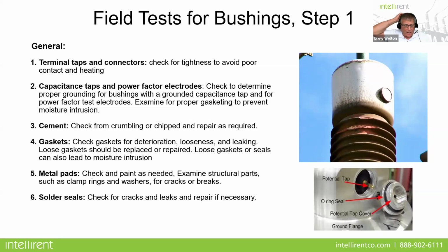And it's funny, I was talking to a colleague just a couple of weeks ago, and he went on site on a recently commissioned transformer to determine why the differential relay tripped. And when he got on site, two things. The first thing he noticed was that all the bushing clamps on the top of the bushing were all loose. They were all just hand tightened. So, they weren't properly torqued down. The second thing he noticed was that they had a rolled CT secondary, which has nothing to do with the bushing. It's just a bad practice in terms of hooking up the connections. And the other thing is that the de-energized tap changer switch was halfway between one tap or the other, which could have been really catastrophic. So, we just have to be very, very careful to make sure we're following proper procedures.